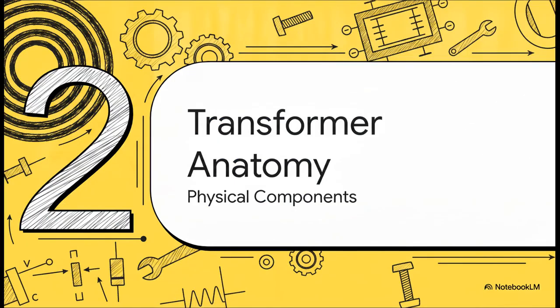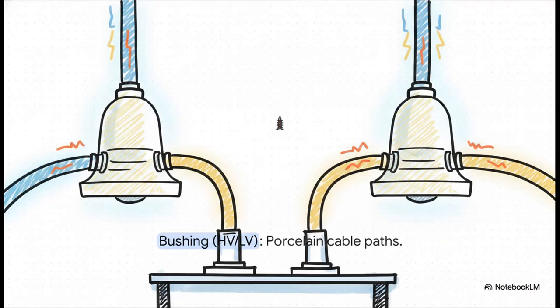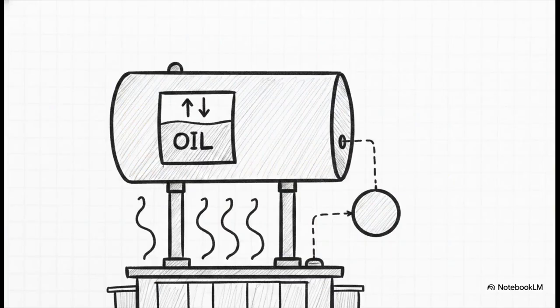Okay, let's break it down in Section 2, Anatomy of a Transformer. We're going to deconstruct this unit and look at the actual physical components you'll be inspecting out there on the job every single day. First up, the bushings. These guys act as vital porcelain insulators for the high and low voltage cables entering and leaving the transformer. They give the electrical current a safe path to pass right through the grounded tank, keeping you from dealing with a massive short circuit. Next, look up top.